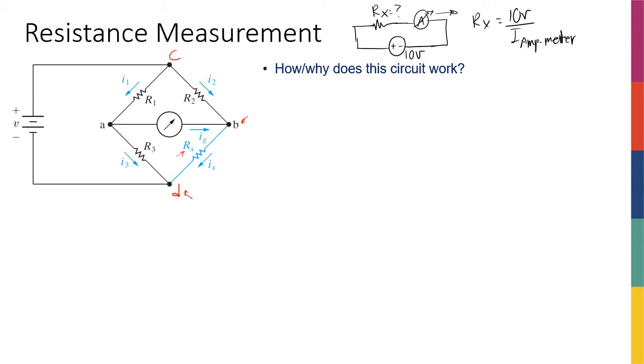Okay. So the way that we are going to do it is using a circuit called the Wheatstone bridge. It's a very well-known circuit in electronics and instrumentation. It's useful to measure resistances in the range of 1 ohm to 1 mega ohm. Anything smaller than 1 ohm, we're getting into the domain of ideal wire resistance, so it's going to be tricky.